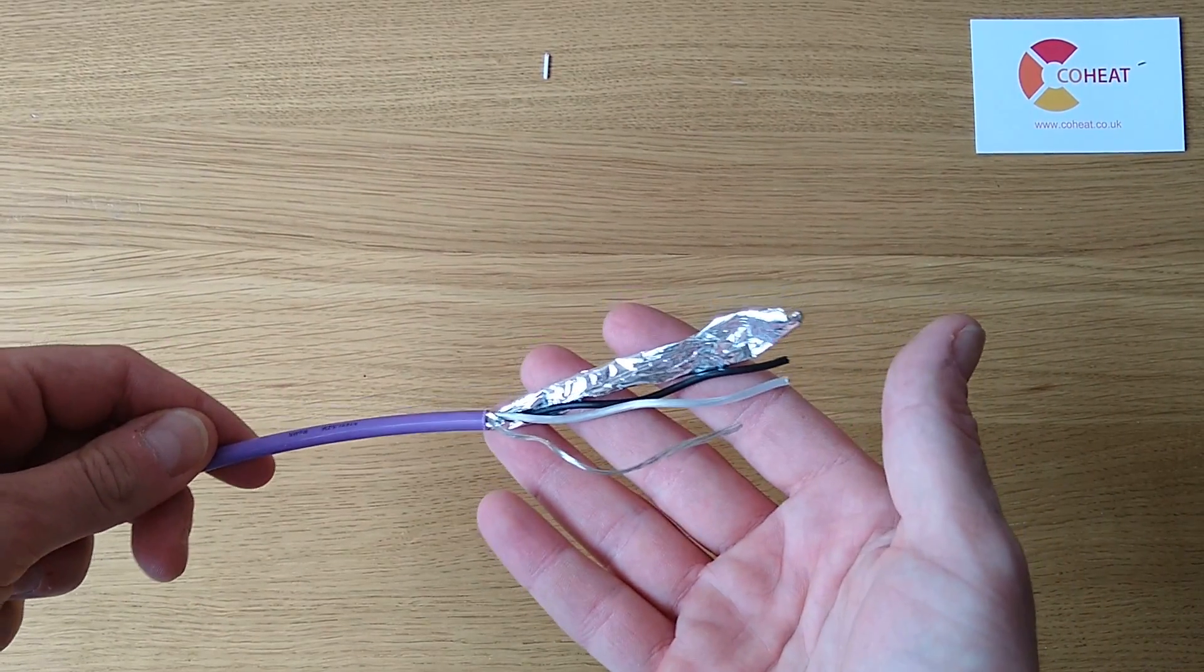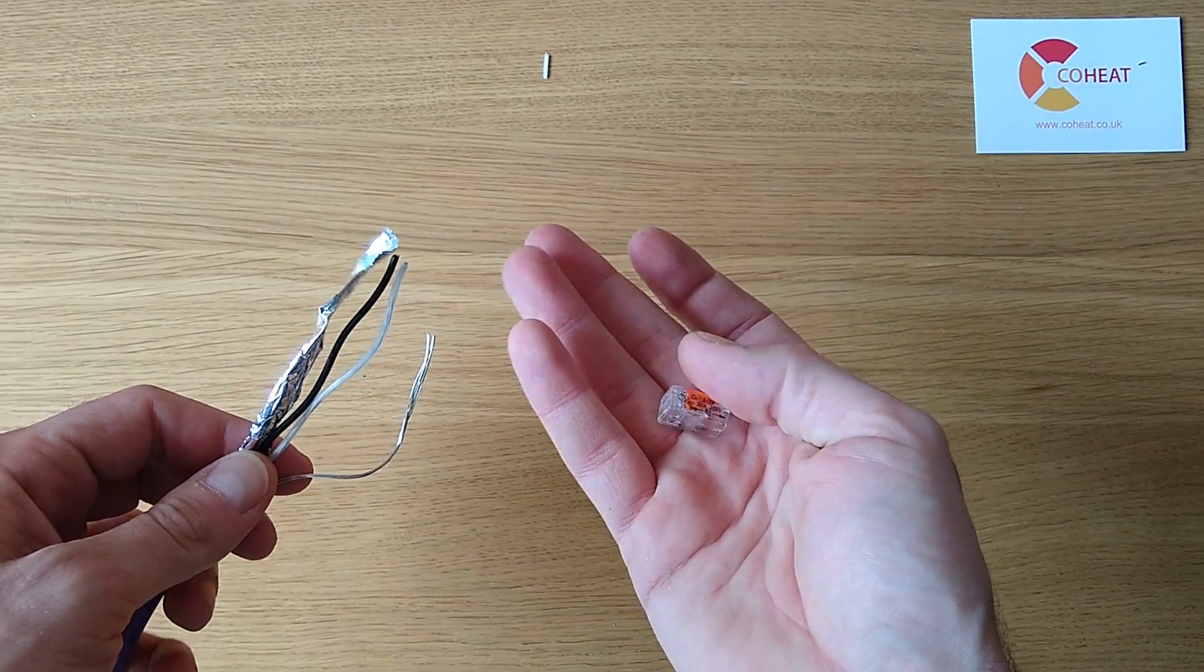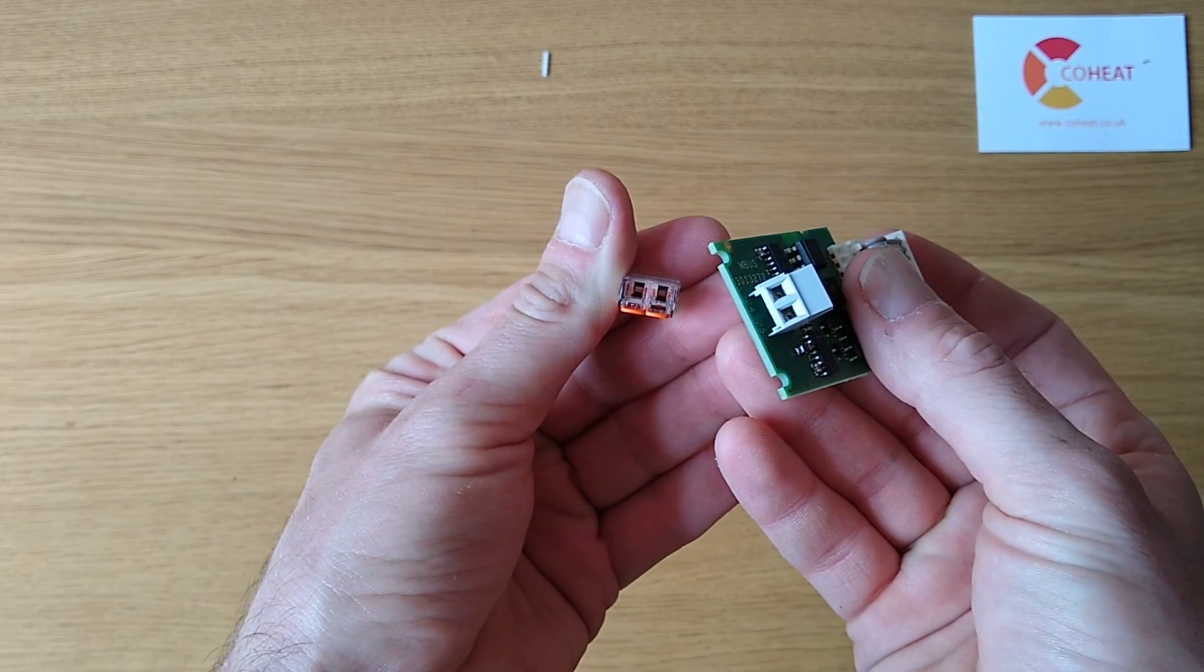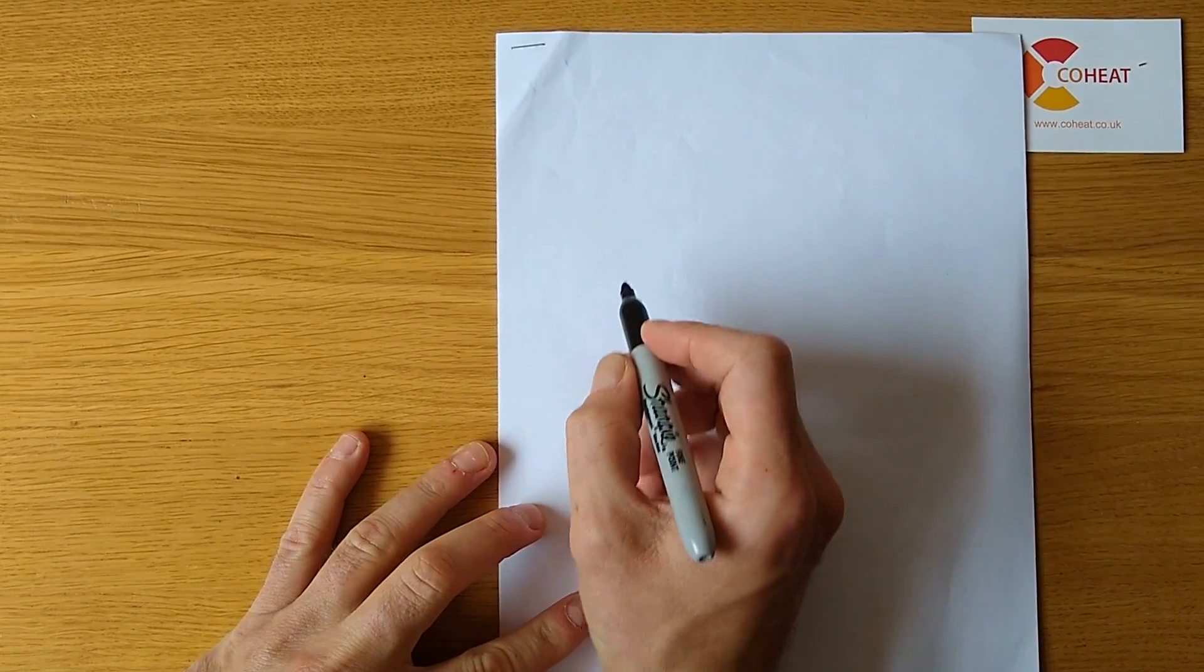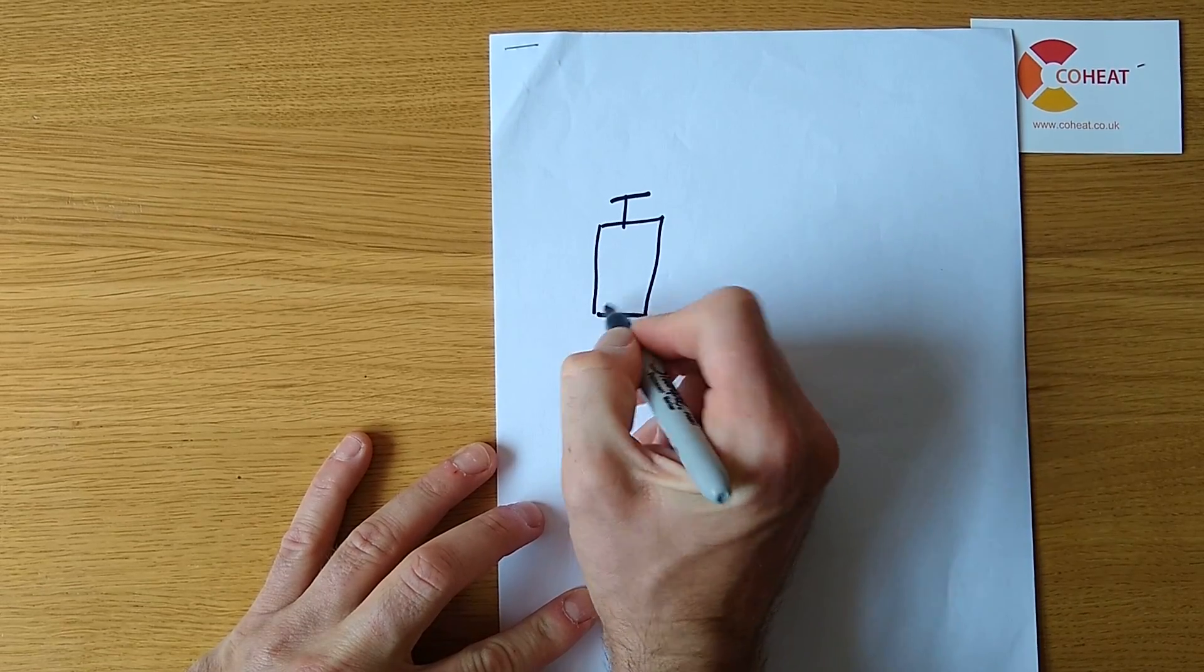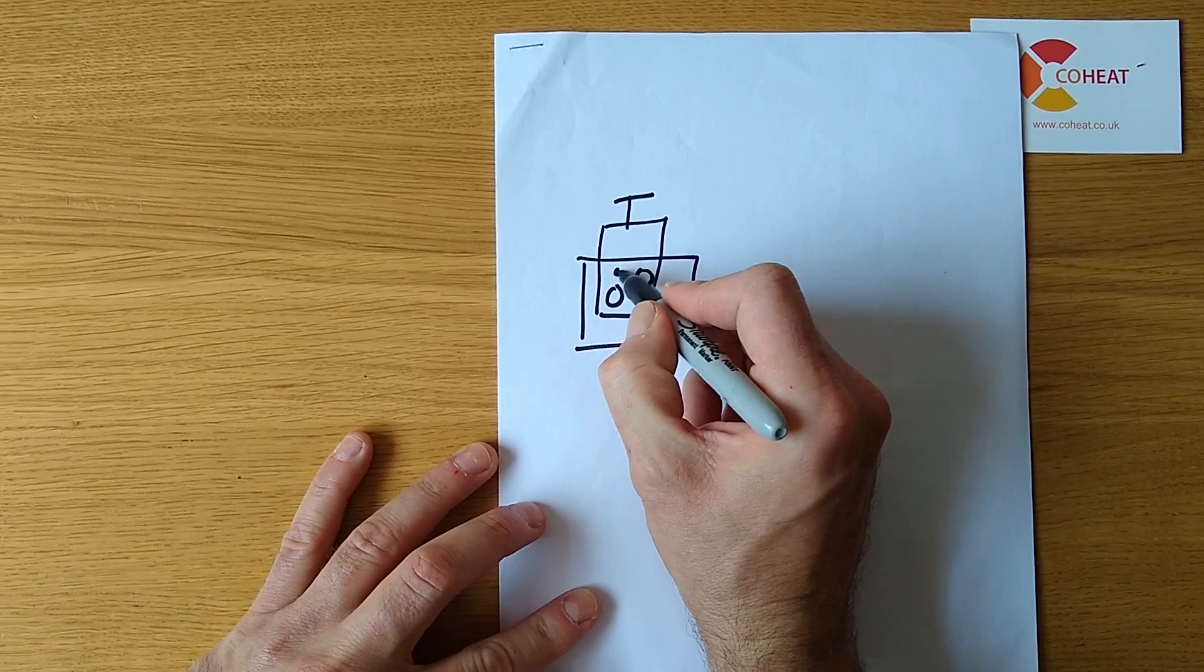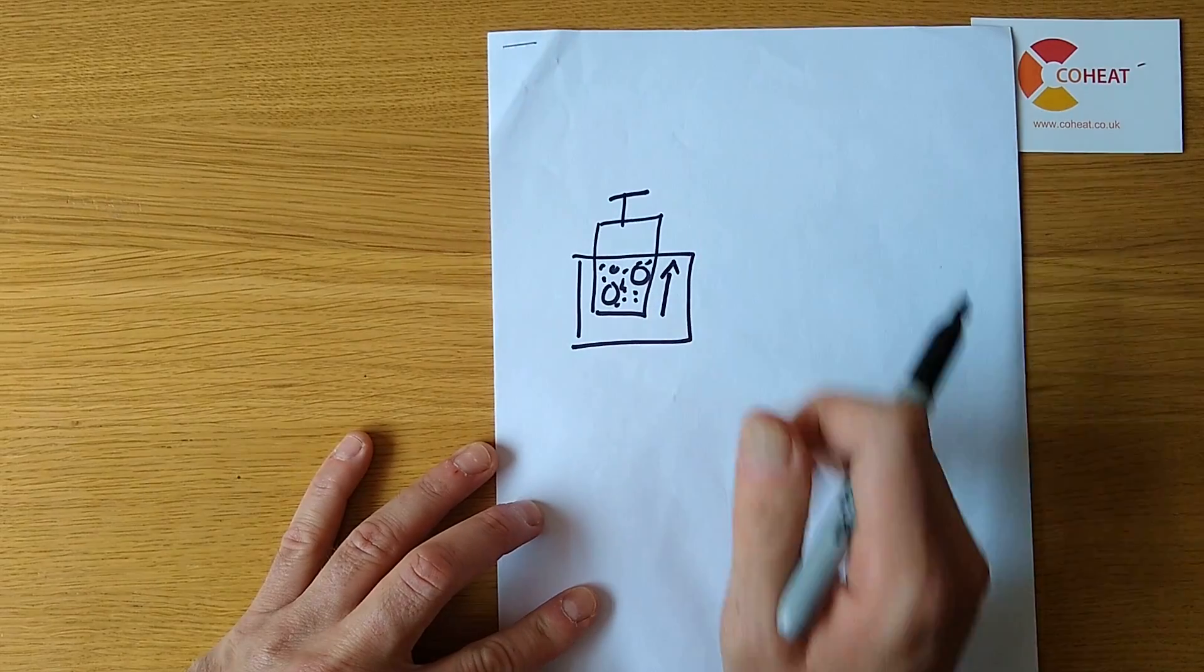If you're using this Belden 8760 style of cable, I would always use Wago 221s. The reason these and the data cards supplied with the premium heat meters work is this style of connection. The terminal block has a screw going into a frame, your cables all sit in here along with all the squiggly strands that are running astray, and this clamps the entire assembly.